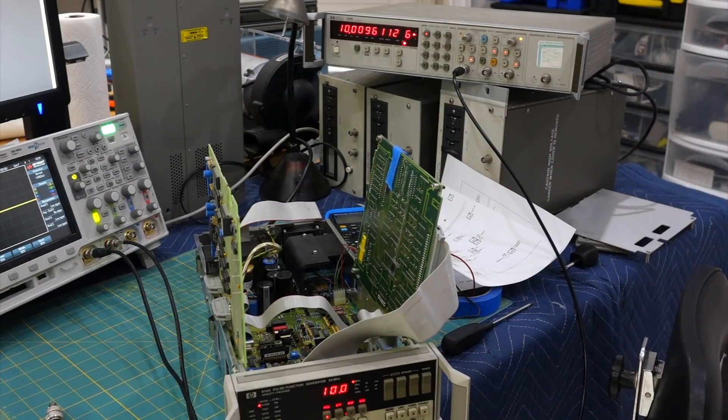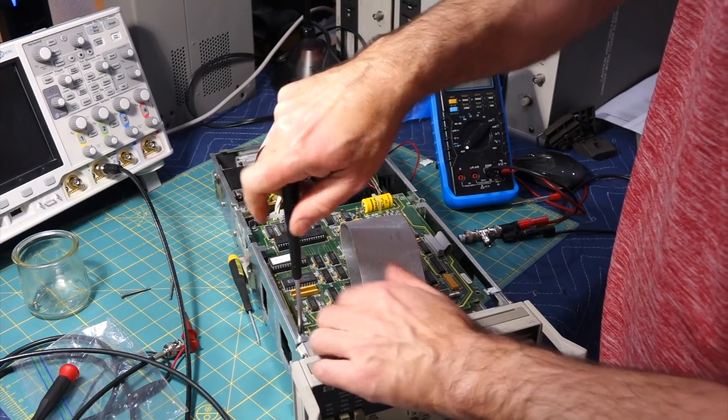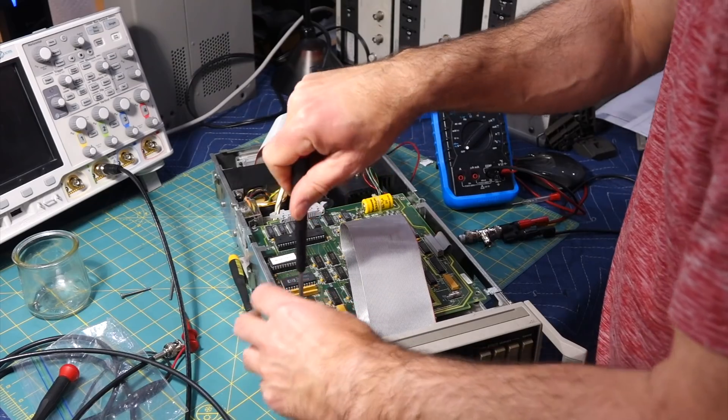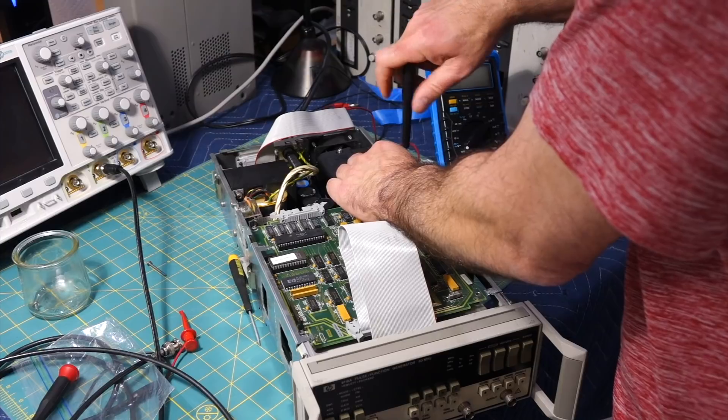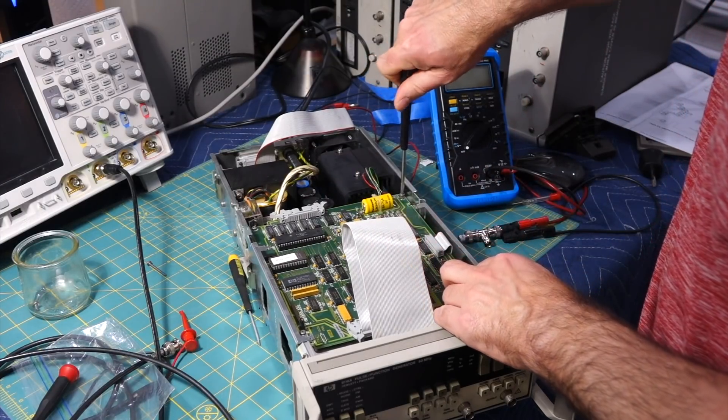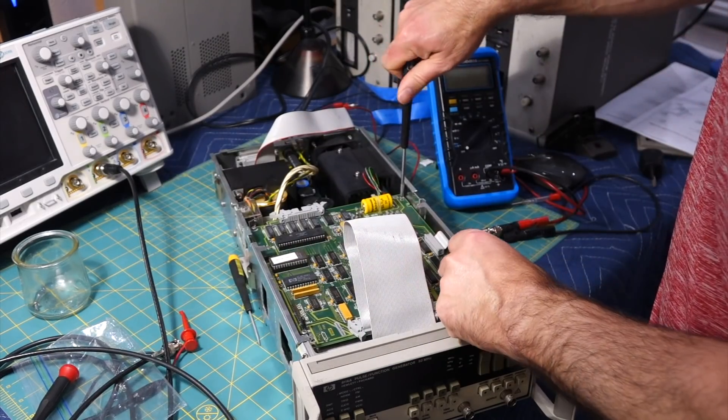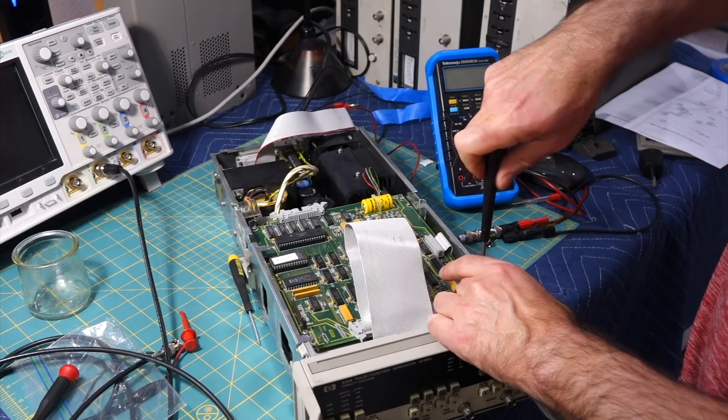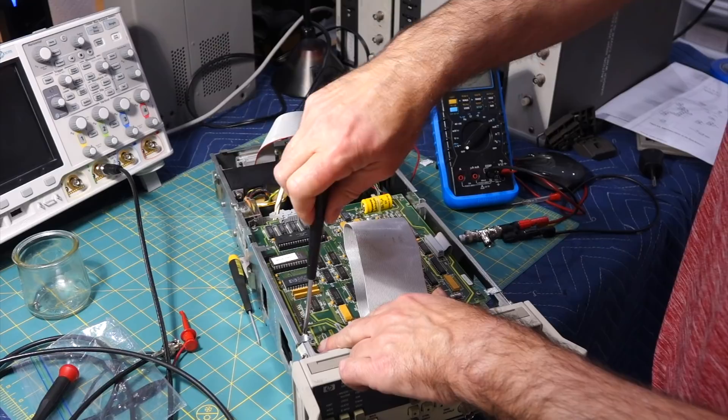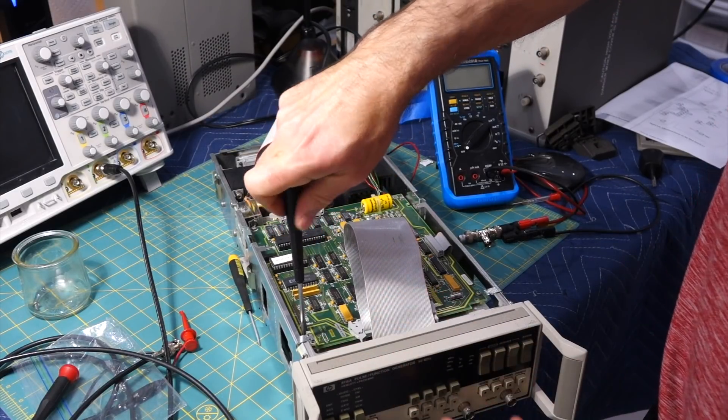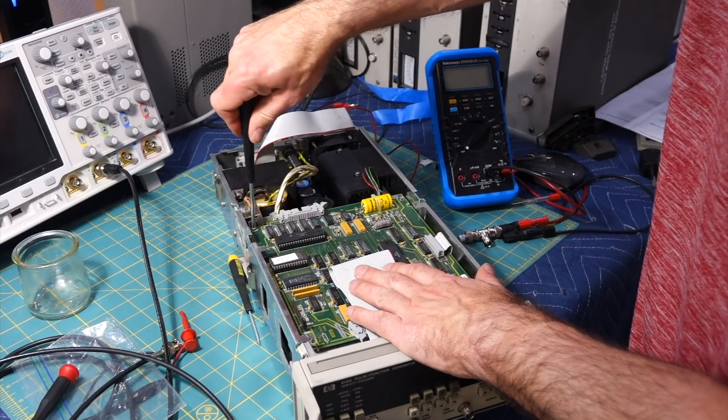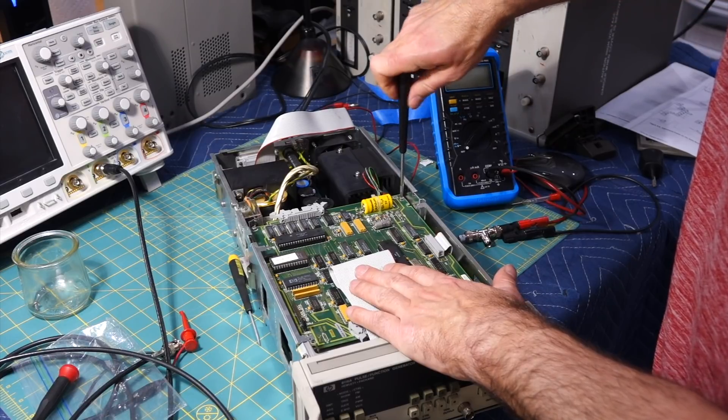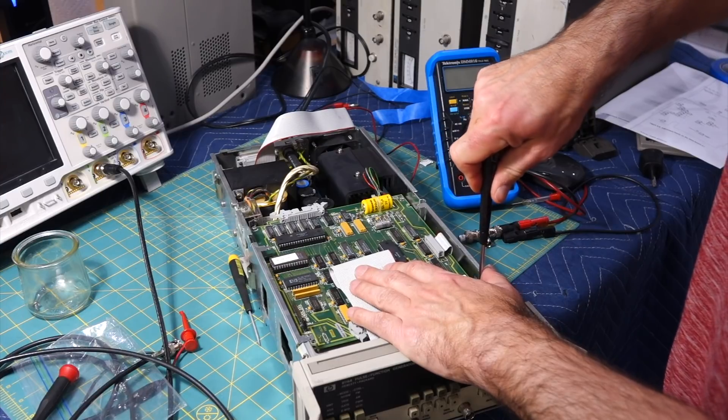So I'm back in calibration here. Boy, that was very much more analog-y than I expected in this instrument. I hadn't realized it was really an analog VCO, an analog everything, controlled by digital electronics, but the instrument inside is analog. And this is why I couldn't achieve the frequency precision that I expected. It doesn't advertise much. It advertises only three digits, so that makes sense. But at least now, it's not completely off as it used to be.